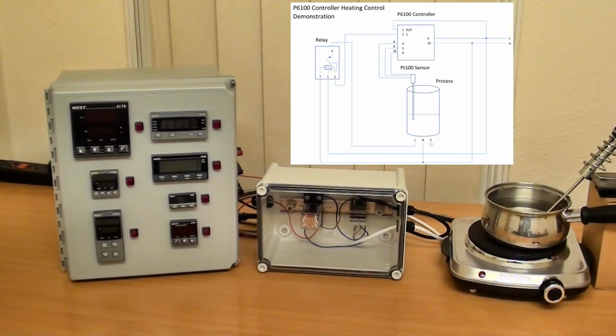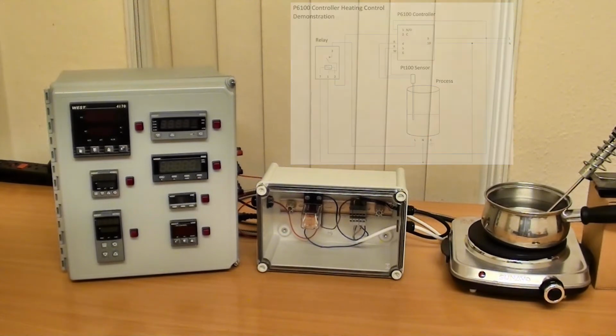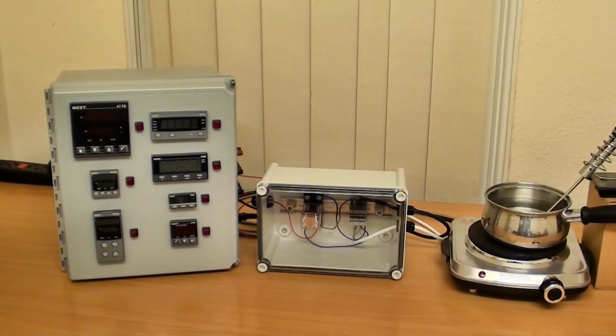Consequently, the set point ramping feature can reduce thermal shock to the process and reduce overshoot on startup or set point changes. Once the ramping set point reaches the target set point, the set point ramp rate disengages until the set point is changed again. The first demonstration will show how the process reacts with the set point ramping feature disengaged. The second and third demonstrations show how the process reacts with the set point ramping feature engaged at different ramp rates.